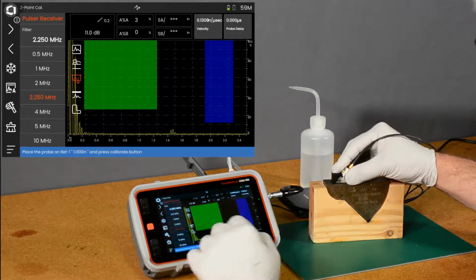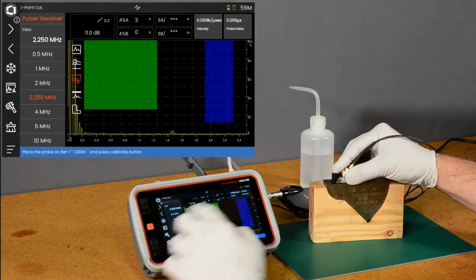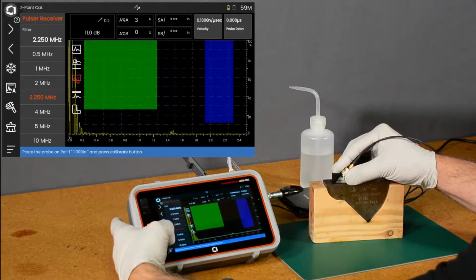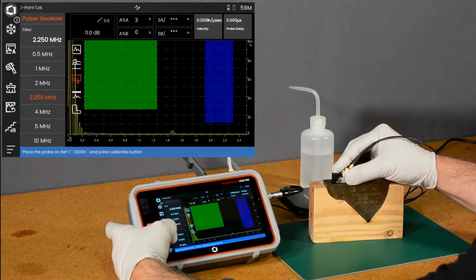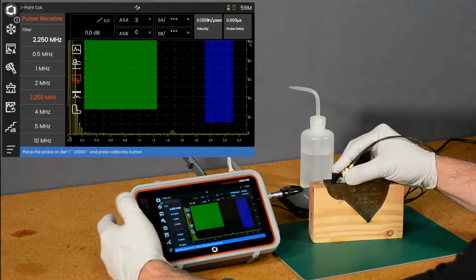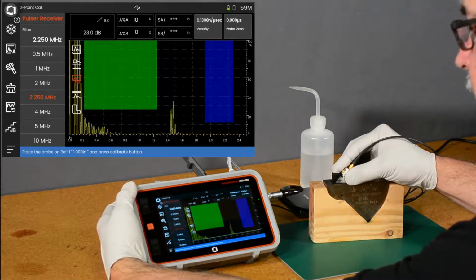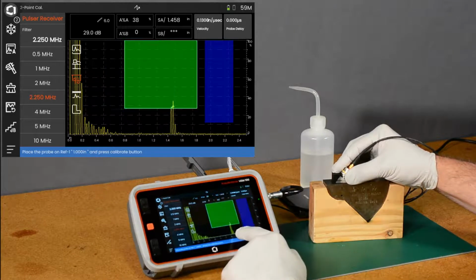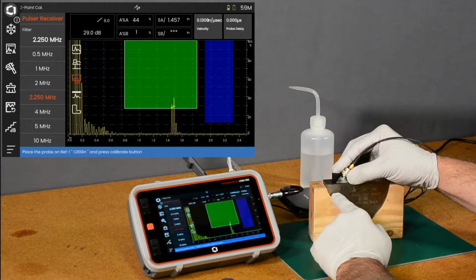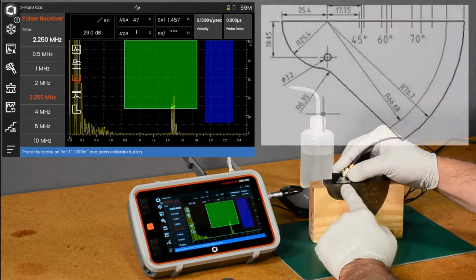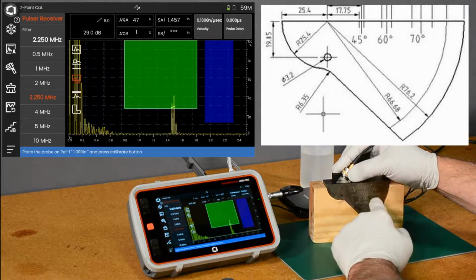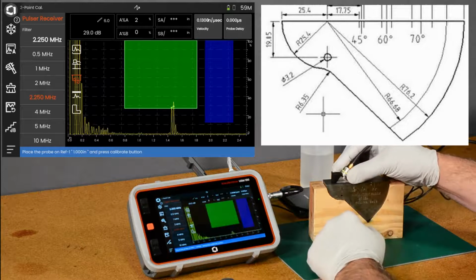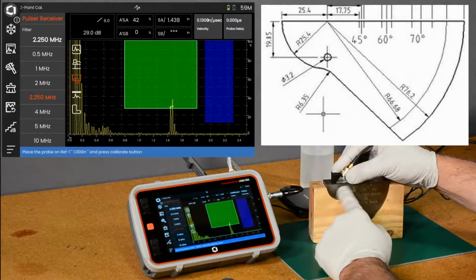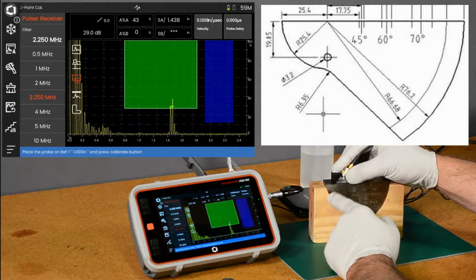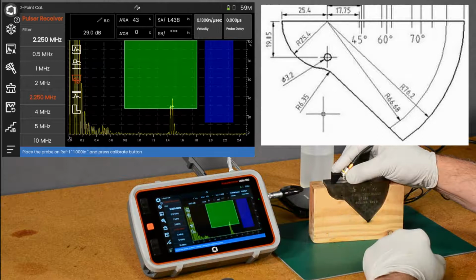And we start to see now our echo from the block. Let's take our gain up, change our dB step to some coarser steps, 6 dB steps for now. Give the gain tap on the back. Okay, and here's our echo from this 1-inch radius of the DSC block. Now the DSC block gives us a 1-inch radius and a 3-inch. If I turn the probe around and shoot this direction, I get 3-inch. When I'm on the 1-inch, I actually get an echo from 1 inch and also an echo from 5 inches. So 1 plus 3 plus 1 gives me 5.